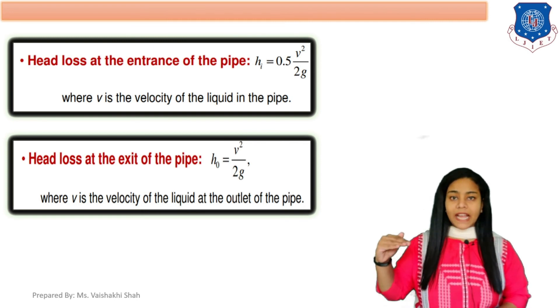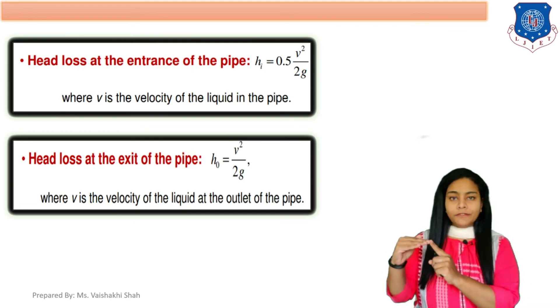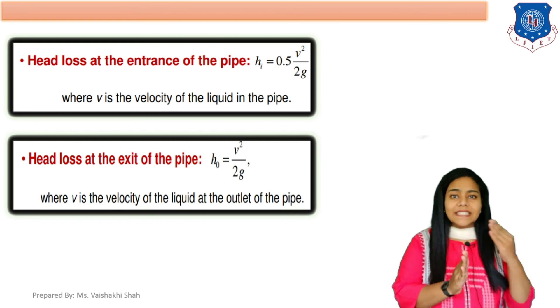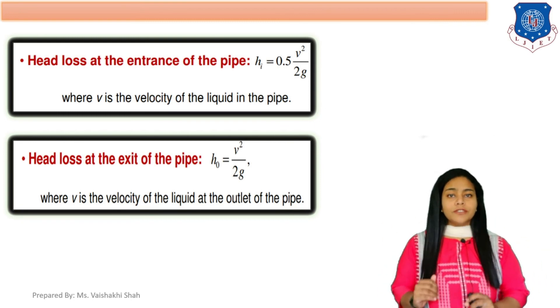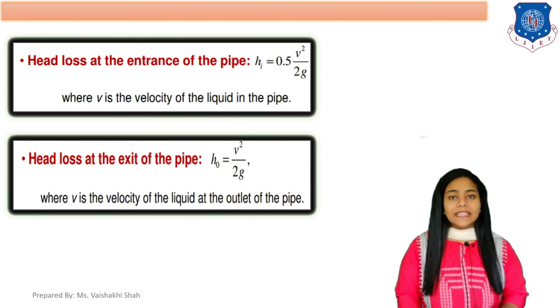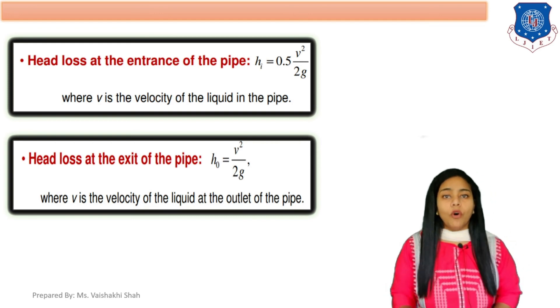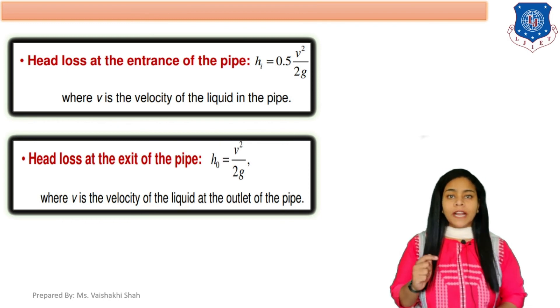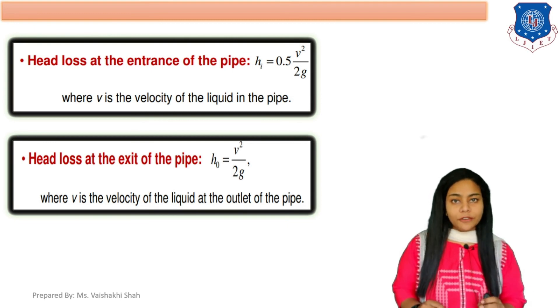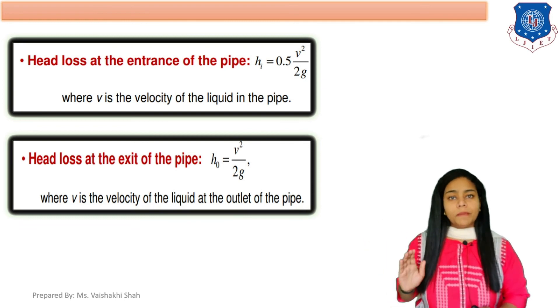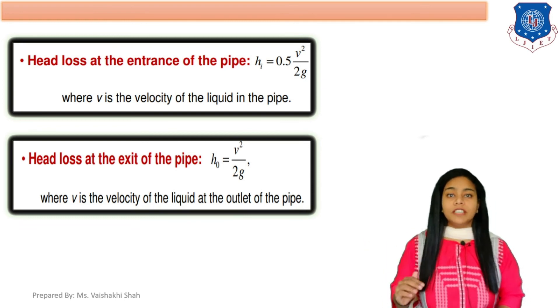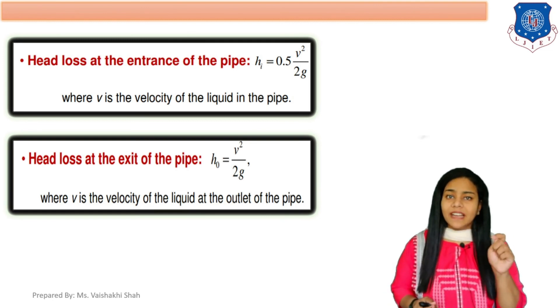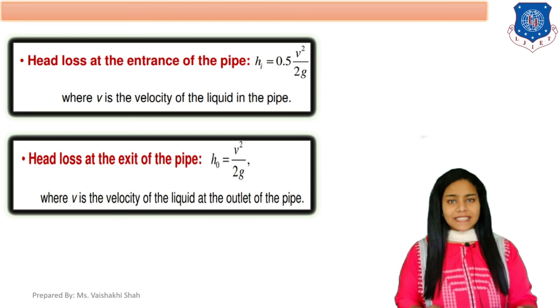Another equation: head loss at exit of the pipe. When fluid enters there is head loss at entry; when fluid is passing there is head loss due to friction; and when fluid exits from the pipe there is also head loss called head loss at exit, indicated as ho (outlet). The equation is ho = V² / 2g. In both equations, V is the velocity of liquid flowing in the pipe — at entry and at outlet respectively.